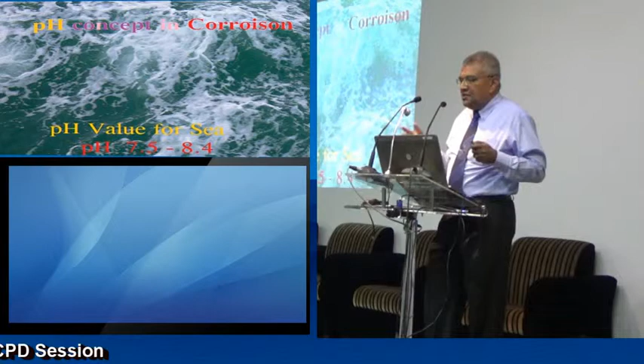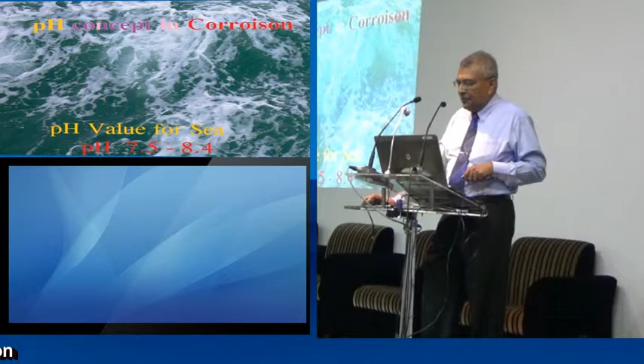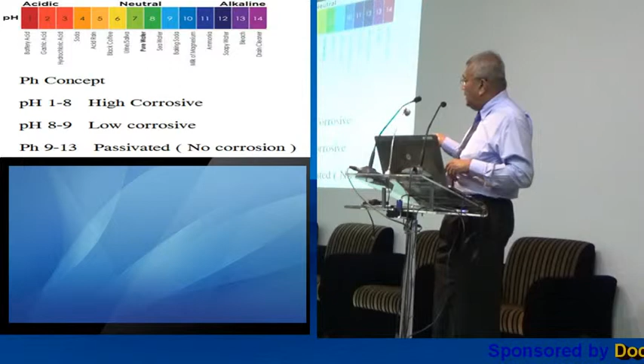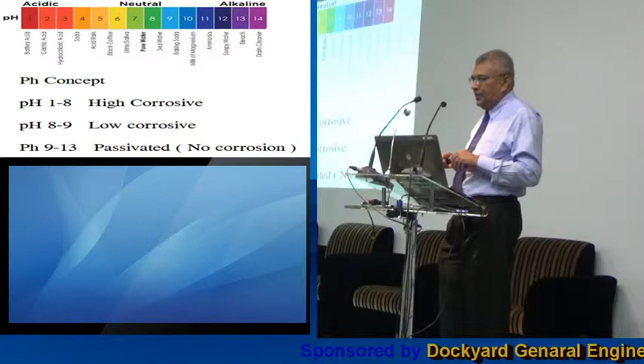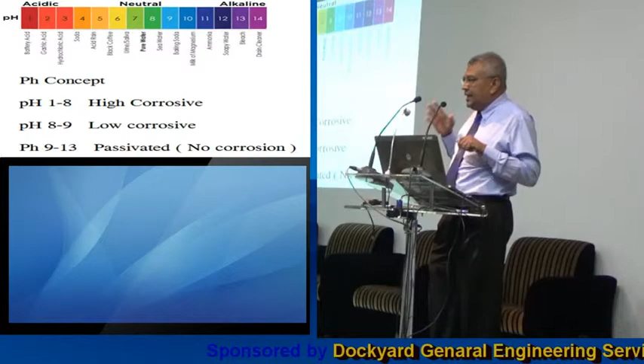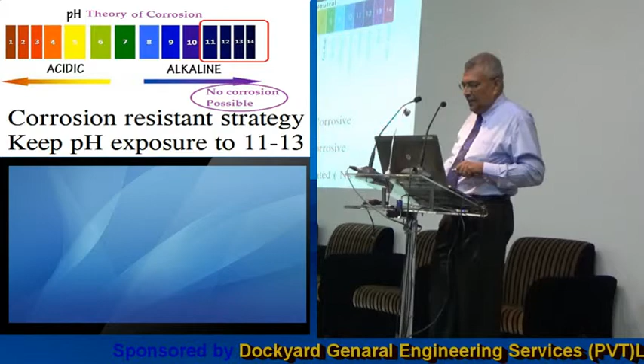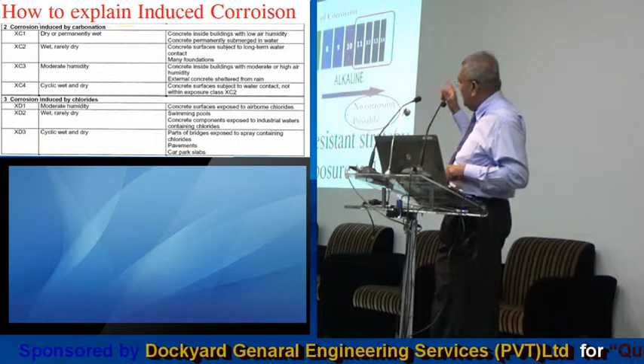The pH connection - seawater has a pH of 7.5 to 8.4. Everybody knows the general pH scale: acidic, neutral, alkaline. But for corrosion, the pH connection is different: pH 1 to 8 is acidic and highly corrosive, pH 8-9 is low corrosive, pH 9-13 is non-corrosive. This is called passivation - if you can maintain your pH value at 11 to 13 or 14, you will never corrode the steel. No corrosion is possible at pH 11, 12, 13, 14.